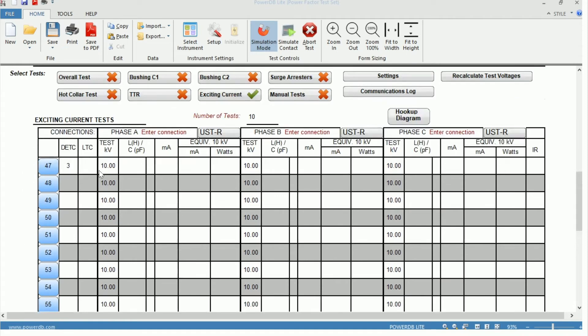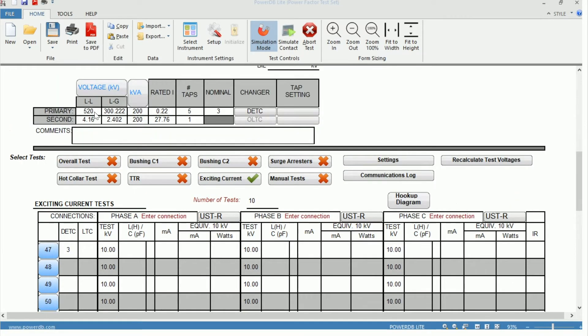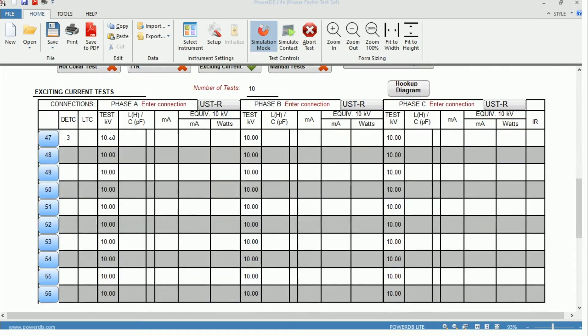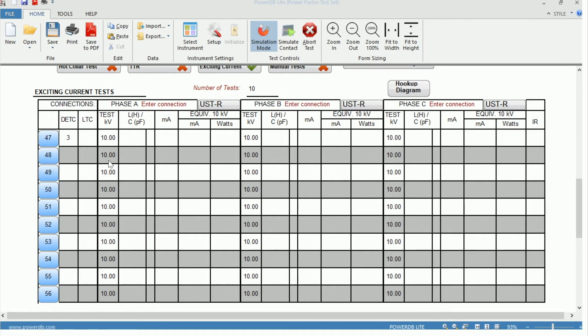Moving over, we can see the test voltage is already populated. It's populated because we've input the voltage for the transformer, so we already have all of the information as far as voltage and power rating. So it will automatically populate with the appropriate voltage. We can also see the inductance or capacitance measurements in either henrys or picofarads, and then the actual measurement of our excitation current, as well as the 10 kV equivalent. We're already testing at 10 kV because the primary side is rated over 10 kV. But in the event that you're not able to test at 10 kV, it does give the 10 kV equivalent.